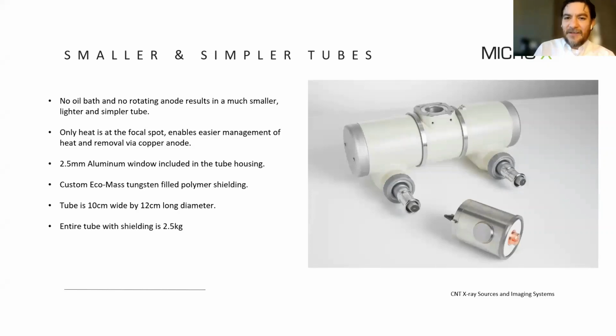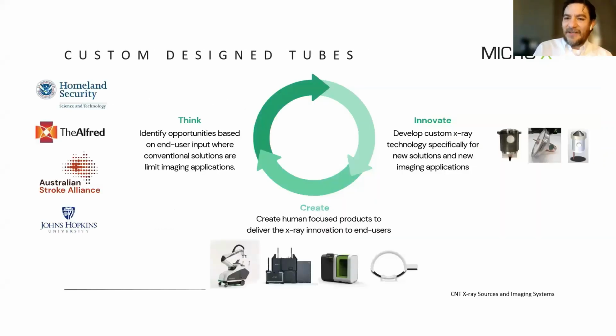And then finally, we think about the tubes differently. Based on these advantages of varying the focal spot, of electronically controlling, of a simpler tube, rather than making X-ray tubes with a specific performance, we have identified applications where X-ray imaging is limited, or there are challenges in using conventional X-ray imaging. We develop custom X-ray tubes using these advantages for a specific solution, and then work to use that custom X-ray tube to design products that have specific workflow and features to meet the applications that have been identified.